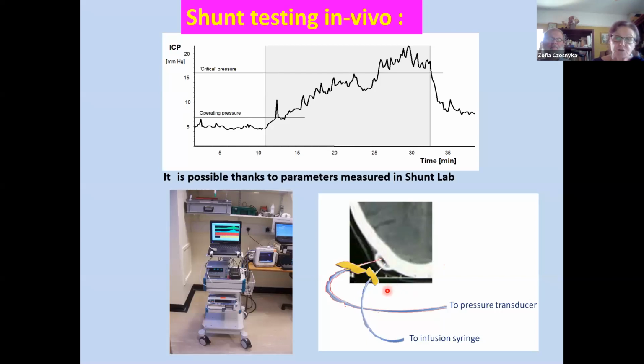The advantage of the infusion test, we can see here the result, is that not only do we evaluate the baseline state, but we can also assess how the system is responding to an extra challenge of the infusion. On the basis of the laboratory testing, the appropriate values for each valve and each setting level can be calculated, as shown here. And this is our reference in valve assessment. All equipment can be mounted on a small trolley: infusion pump, pressure monitor, computer with ICM Plus software. This trolley can be easily taken to the patient's bed anywhere in the hospital.